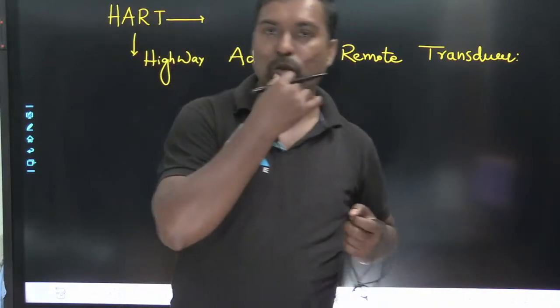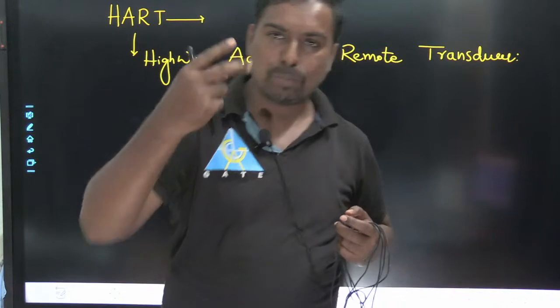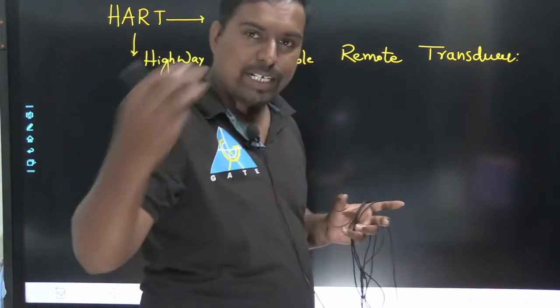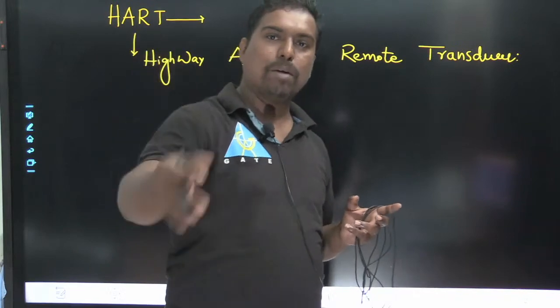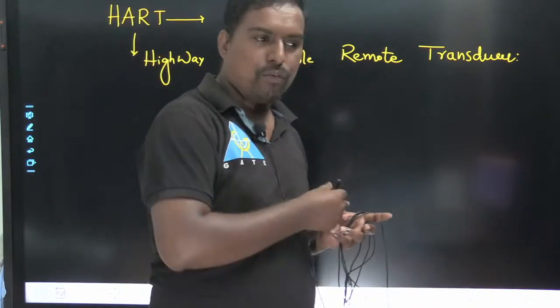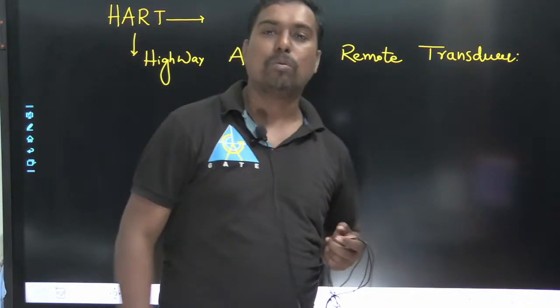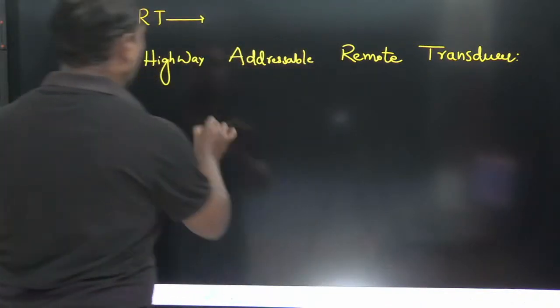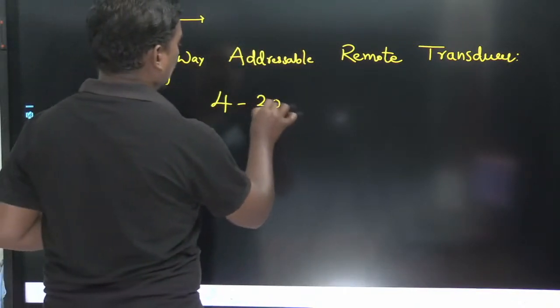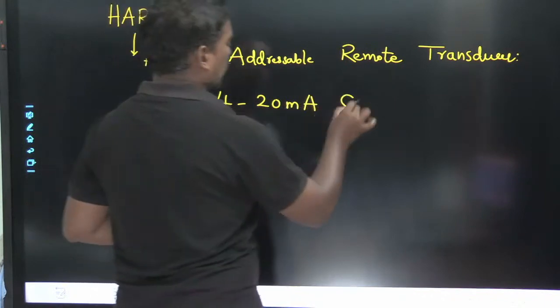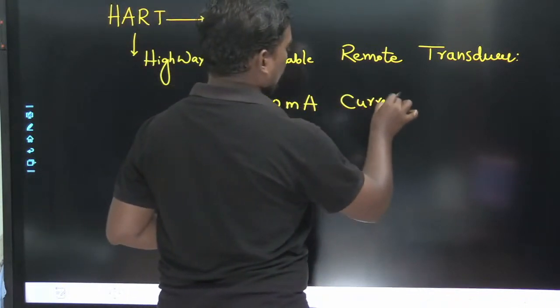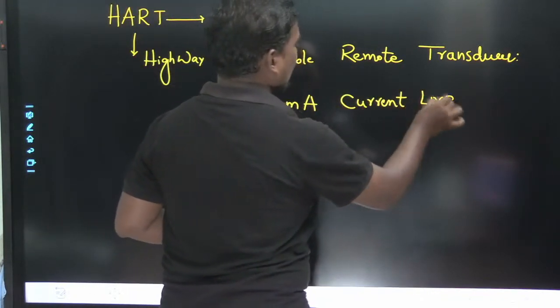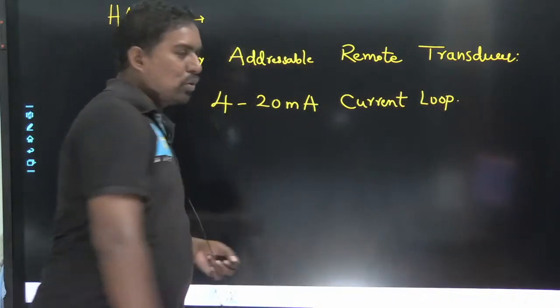Wired: when two field devices are connected using two wires, a field device is connected to a PLC and we get the information of level, minimum and maximum, in the form of one loop. What is that loop? Current loop, my dear, the 4 to 20 milliamperes current loop. Any signal is adjusted on this 4 to 20 milliamperes.